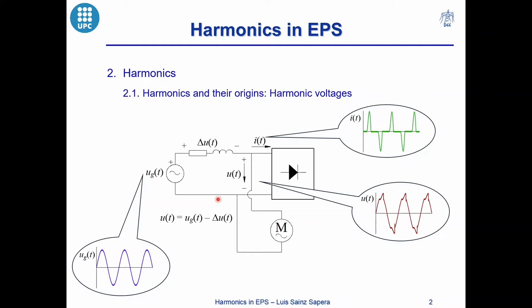We have the same circuit as the previous one, but including the impedance of the grid, where we have the voltage drop. In this situation, the voltage at the load terminals is equal to the sinusoidal supply voltage minus the voltage drop at the grid impedance. This voltage drop is the impedance times the distorted current consumed by the nonlinear load, plus the sinusoidal current consumed by the linear load. As this current is distorted, the voltage drop is also distorted, and the voltage at the load terminals results distorted with harmonics.